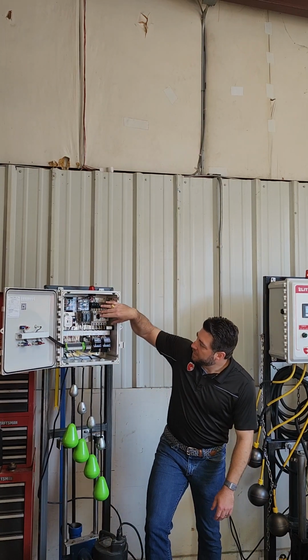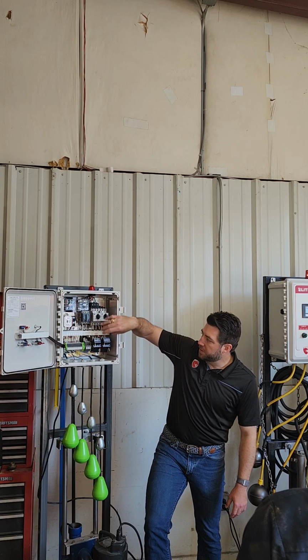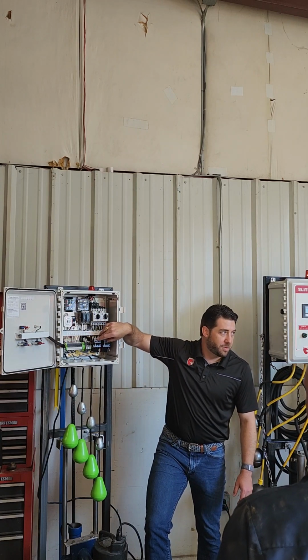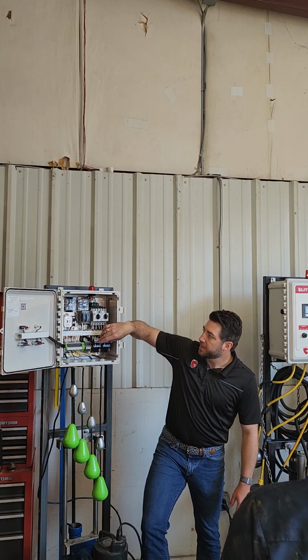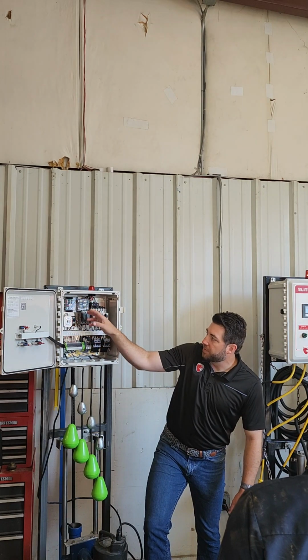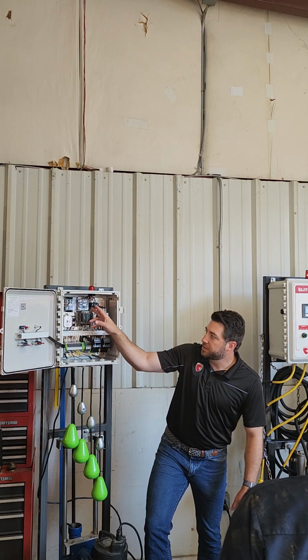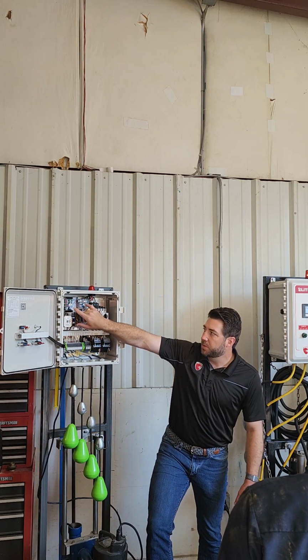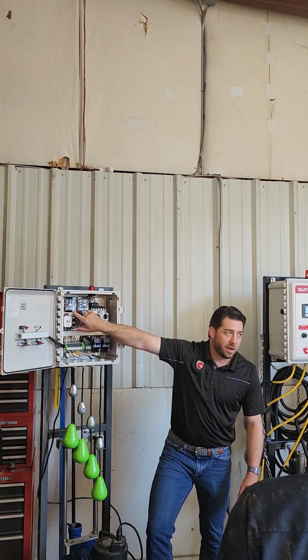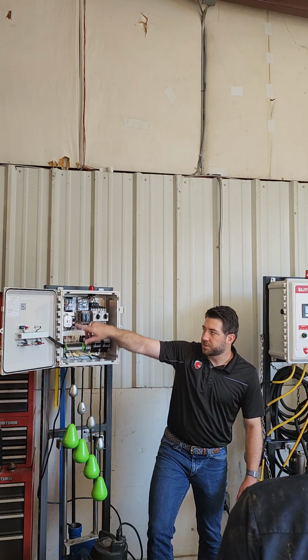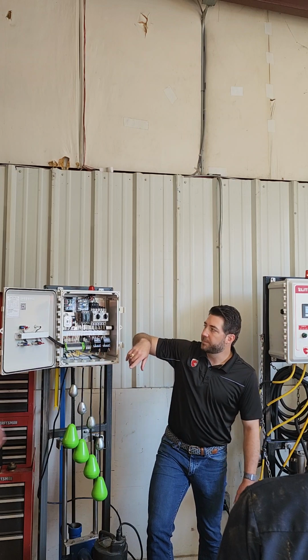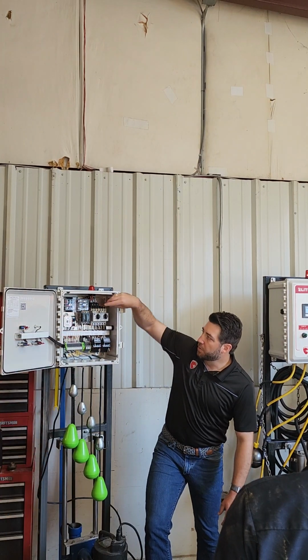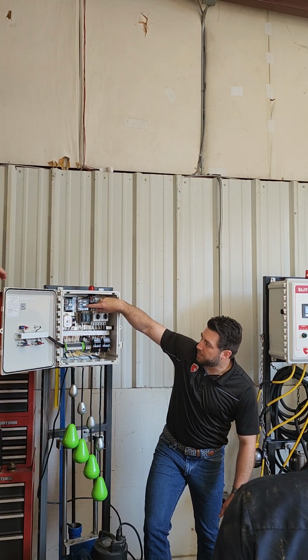So below the overloads are those contactors. Those are what's pulling the motors, or giving the power to the motors. On this side, we're running two of the legs of the high voltage through a control transformer, and we're knocking that power down to 120 volts, and that's what we're using for the control system. So this is the transformer here? Yep.